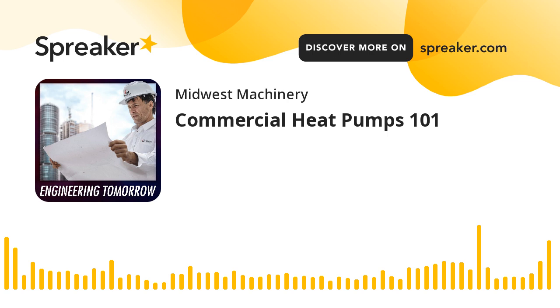So these types of units, like any piece of air conditioning equipment, are going to require service at some point in time. For instance, here in St. Louis, we have a local hotel who's got, I think, close to 300 of these units installed. And what they typically do is, of every size, they'll keep one spare. So if something goes wrong, a compressor goes out, or a fan motor goes out, or a control board goes out, they simply take their spare, install it, take the broken one down to their shop and work on it down there. And that allows them to keep the room open to be rented to customers, so they're not losing any money while they wait for that repair.